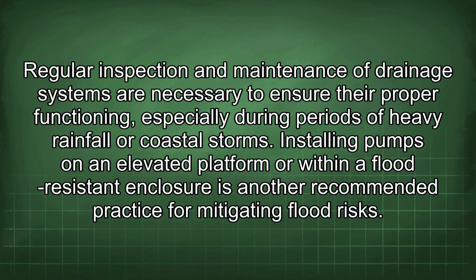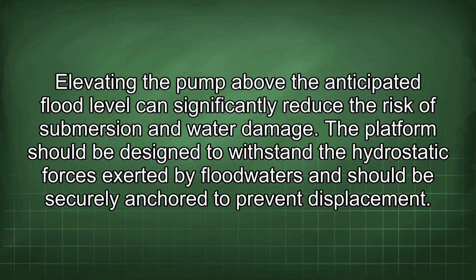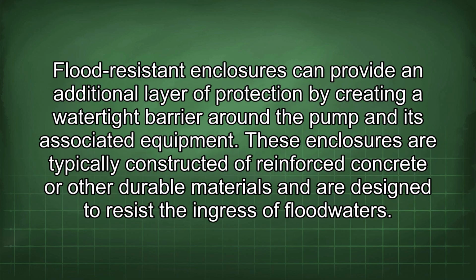Installing pumps on an elevated platform or within a flood-resistant enclosure is another recommended practice for mitigating flood risks. Elevating the pump above the anticipated flood level can significantly reduce the risk of submersion and water damage. The platform should be designed to withstand the hydrostatic forces exerted by floodwaters and should be securely anchored to prevent displacement. Flood-resistant enclosures can provide an additional layer of protection by creating a watertight barrier around the pump and its associated equipment.